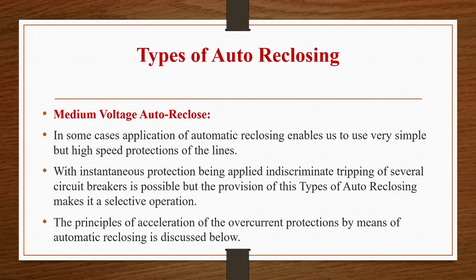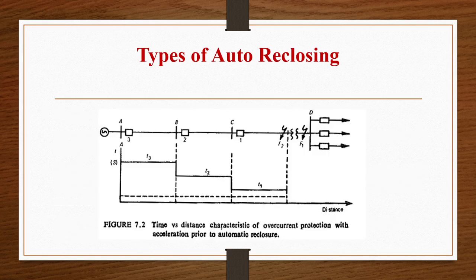So what we are saying here is that application of automatic reclosing enables us to use very simple but high speed protections of the lines. Tripping of several circuit breakers is possible, but the provision of this type of auto reclosing will make it a selective operation. The principle of acceleration of the overcurrent protections by means of automatic reclosing is discussed below. This is a figure showing time versus distance characteristics of an overcurrent protection with acceleration prior to automatic reclosure.